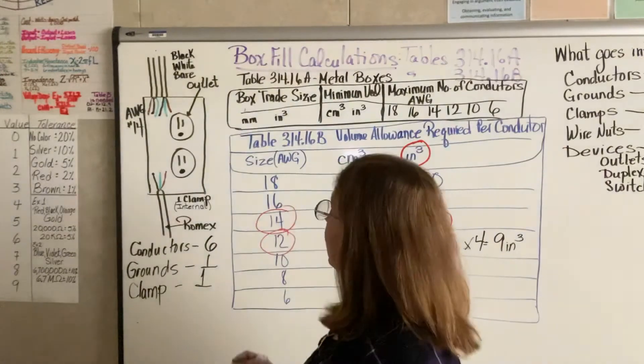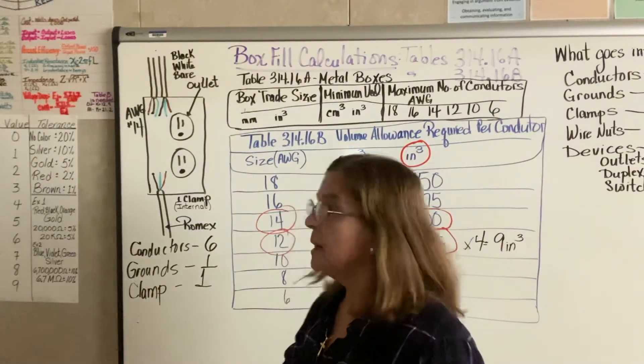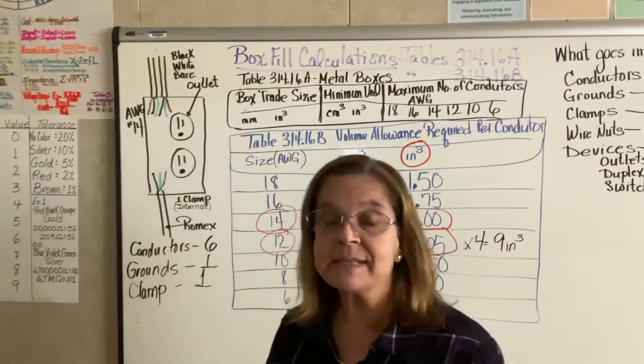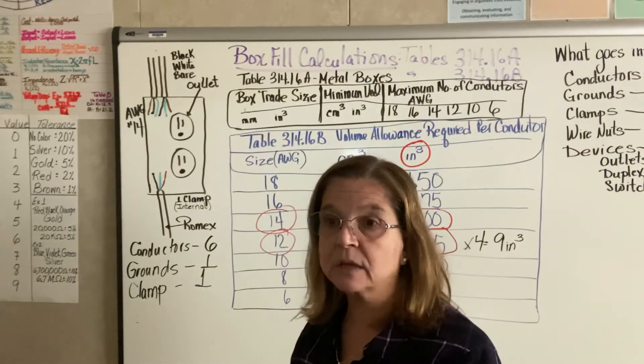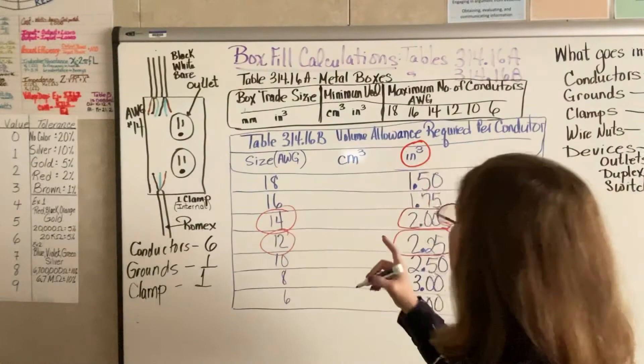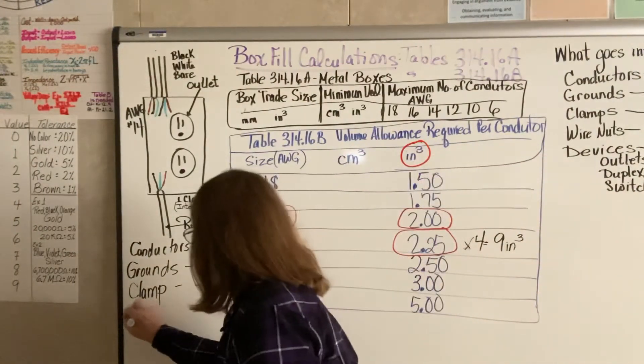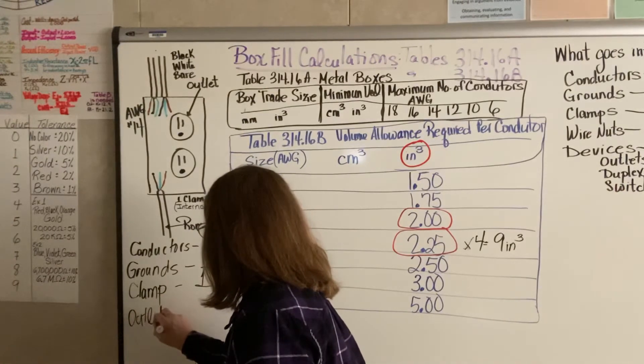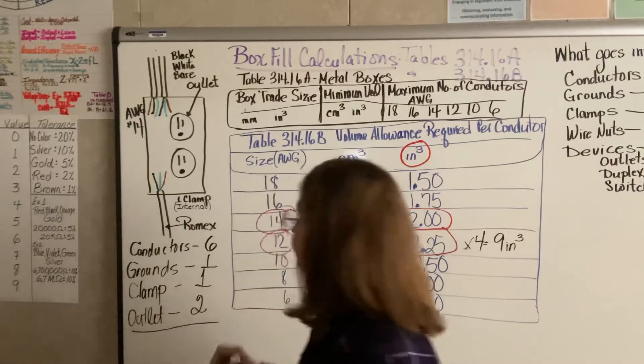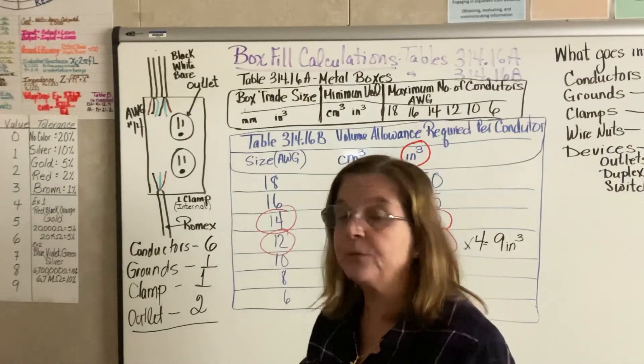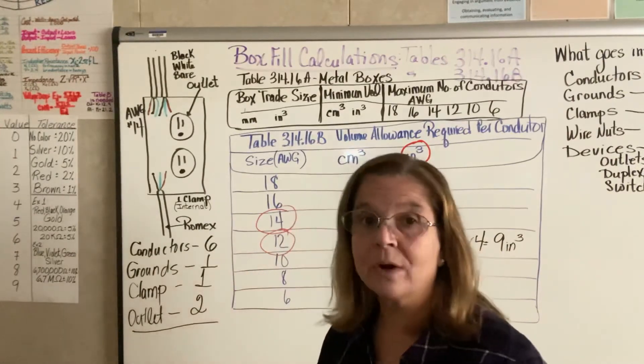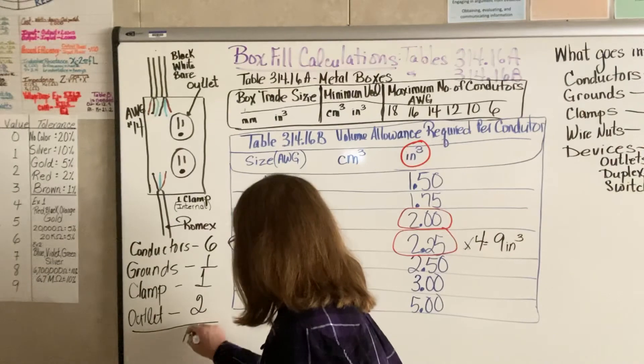And then I probably have a few wire nuts. We don't count those. But I have the actual device itself, the outlet. All devices count twice and you use whatever conductor wire size you have. So in this case we're using size 14. So how many items or pieces do I have to actually account for inside this box? 6, 7, 8, and 2 more is 10. So I have 10 all together.